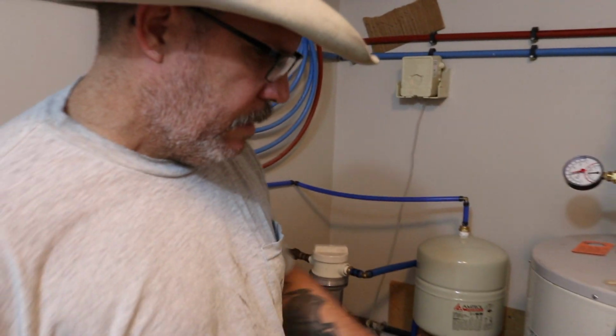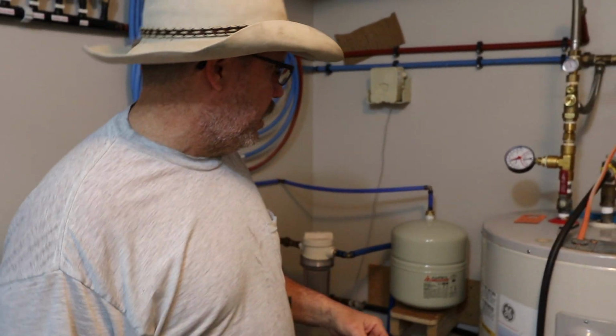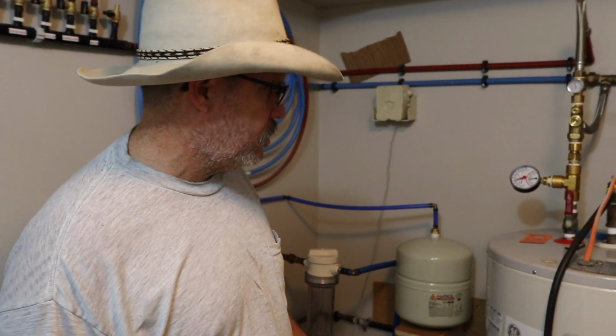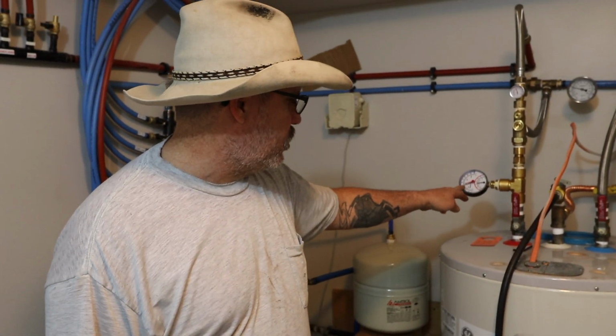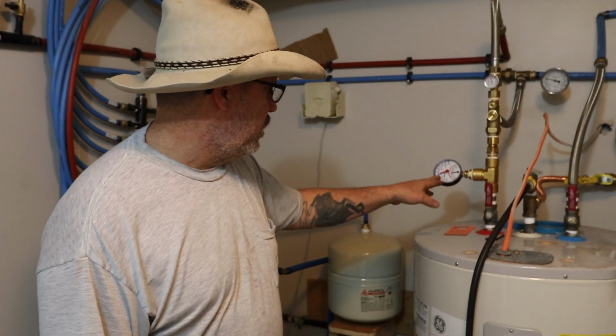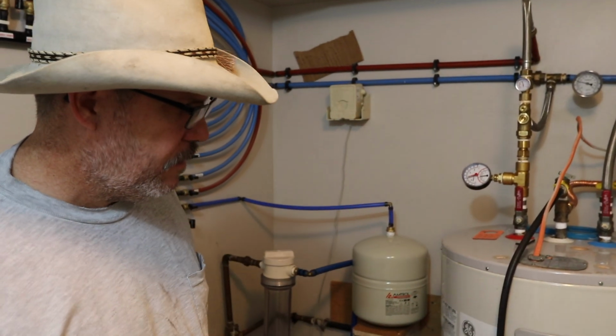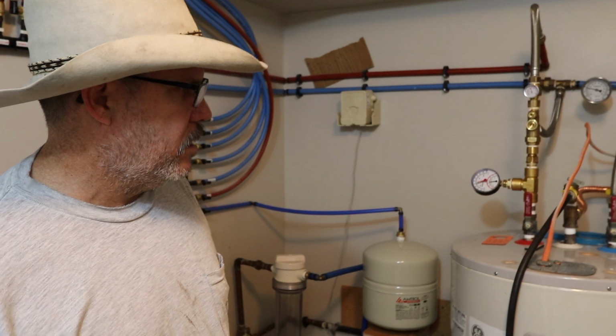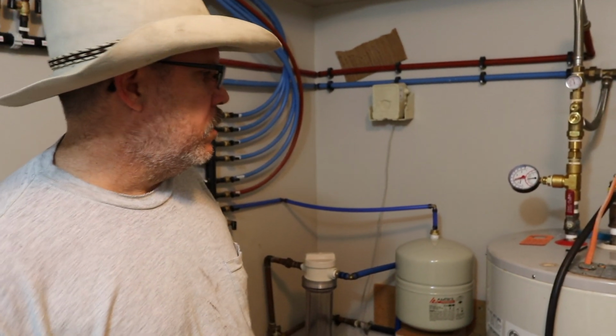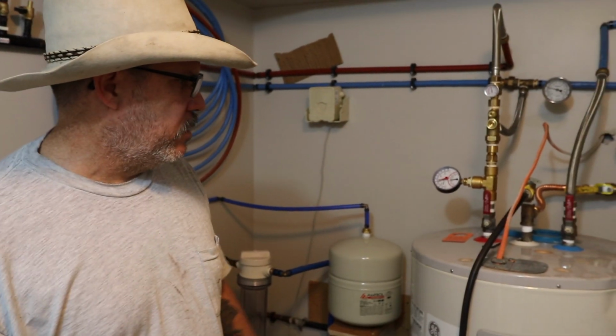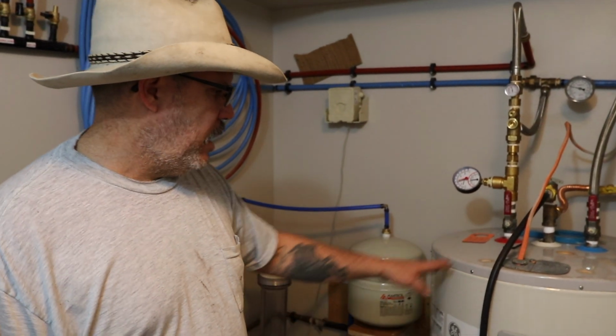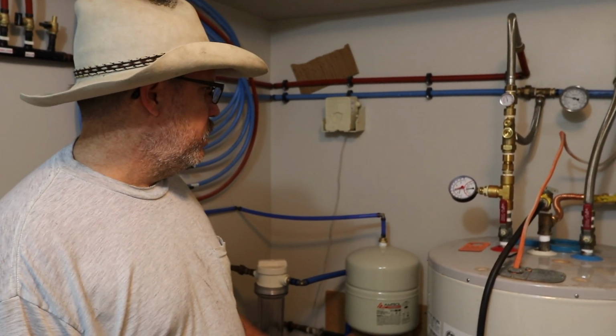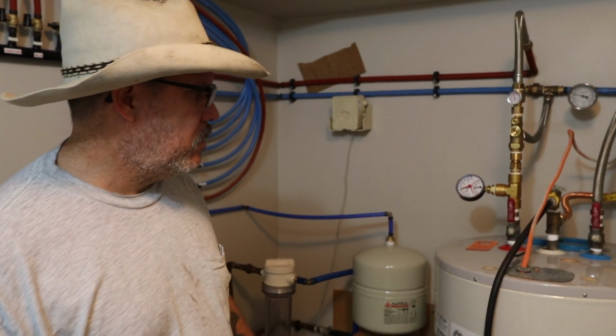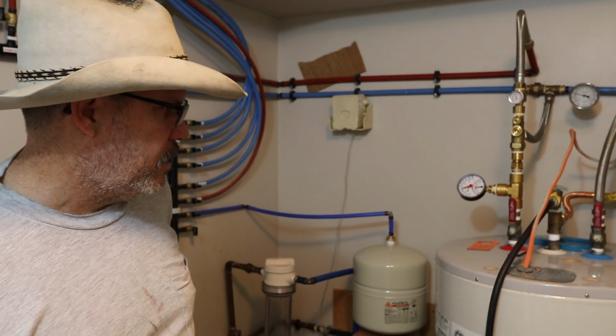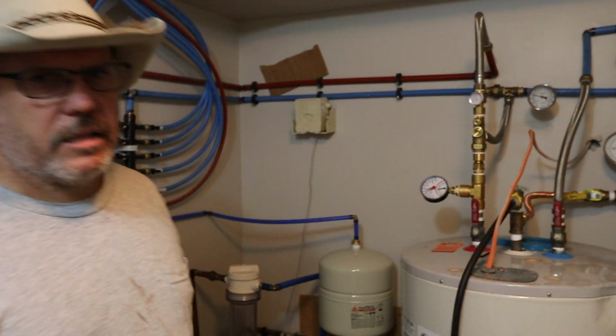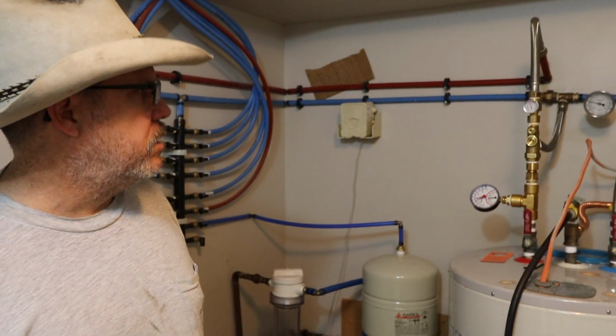The noise you're hearing is my pressure pump. I guess my wife's doing dishes, so she's utilizing water, and we're maintaining that much pressure. If we were on city water and she was running it, I'd probably be at 30 psi in here, and it's just not enough water pressure. But yeah, these things can be really dangerous when you're putting a lot of pressure to them, or you're heating water and running a pressure pump, and you don't want to go over pressure. You can make a bomb out of these things. There are a lot of YouTube videos out there on these things becoming bombs.